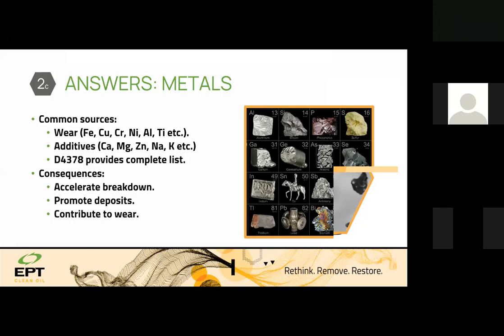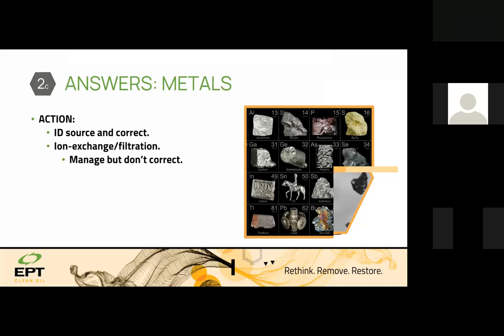how the handling of the lubricant is being done inside the plant, and then let's monitor where and how. For example, if the iron level is going high, you can identify: is it from a bearing or is it coming from outside? If it is a journal bearing failing, you can improve the filtration either with ion exchange, which removes the dissolved metal. So from 20 ppm, 40 ppm iron content inside your used oil, you can remove it.